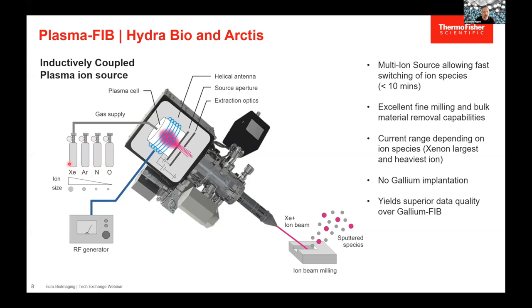Here is basically how a plasma FIB works: different gases come from gas cylinders in the system, go into a plasma cell where energy is coupled in, the gas gets ionized, and then we extract it through optics into the column and focus it onto the sample. For different gases, you can produce different ion beam sizes, each with certain advantages when working with biological materials. Some samples are prone to producing curtaining artifacts, and on soft resins we have effects hard to overcome with a conventional gallium FIB. Here we can switch to a different ion better suited to such samples.